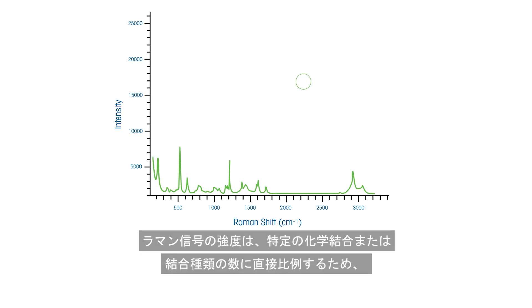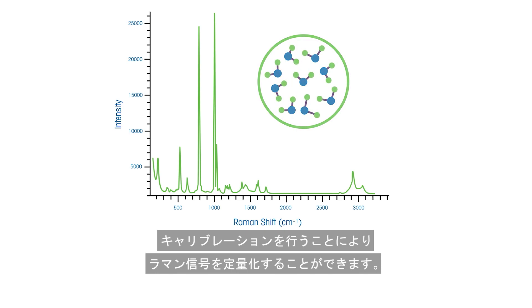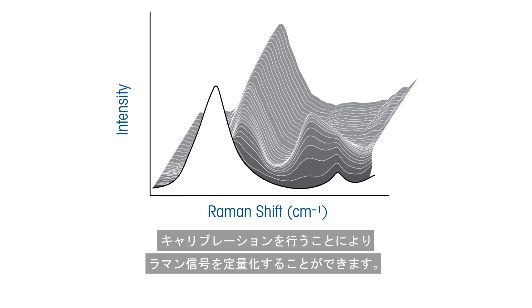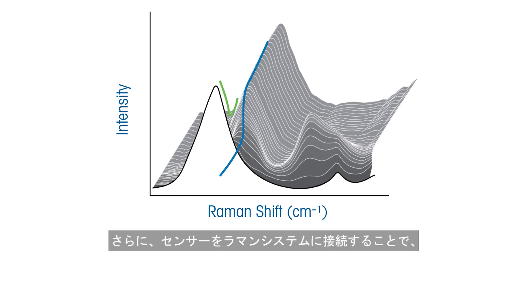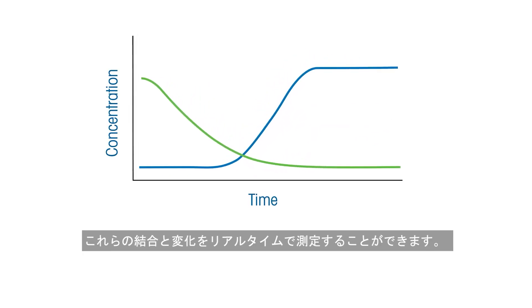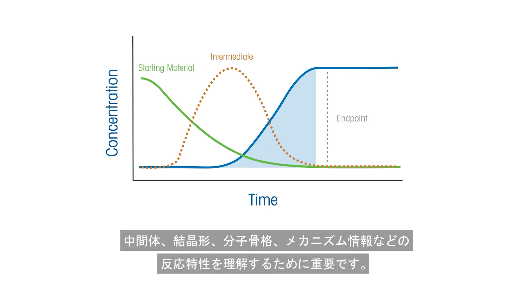The intensity of the Raman signal is directly proportional to the number of a particular chemical bond or bond type, so with calibration, Raman signals can be quantitative. Additionally, when coupling a probe to a Raman system, it is now possible to measure these bonds and their changes in real time. This is valuable to understand reaction characteristics such as kinetics, initiation, endpoint, intermediates, crystal form, molecular backbone, and mechanistic information.